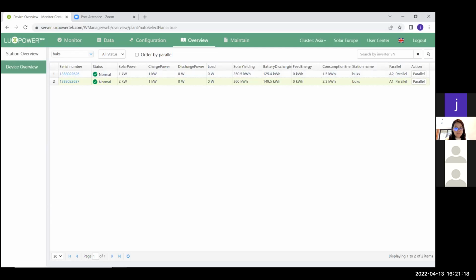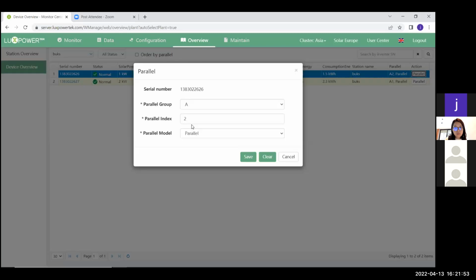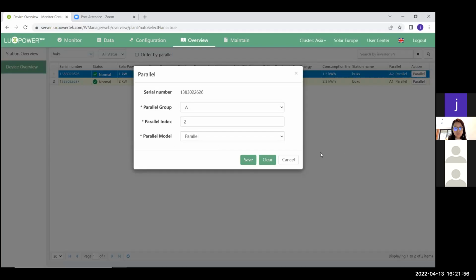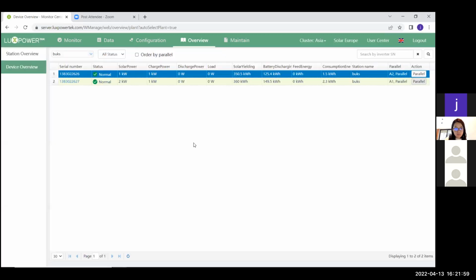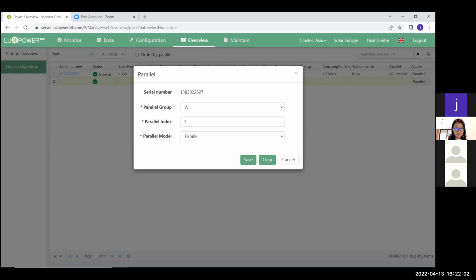Now, once the data loggers are added, you want to tell the monitoring system all these inverters are working together. I would like all the information to be put together, and you only see one monitoring page so that you don't have to jump from inverter to inverter to inverter to see the status of all of them. You can tell the system it is in parallel, and it will combine all the data loggers' information and only give you one page. So to do the paralleling work, from here on, it's quite easy. You go to parallel. All you do is at parallel index, you put 1, save. You go to the second one, you put 2, save, and so on. You go down the list.